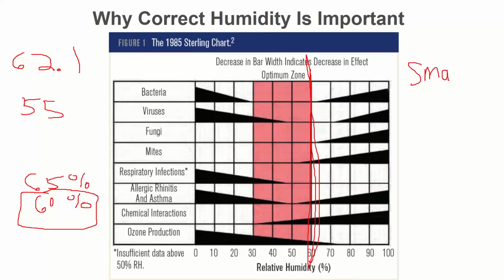The way to do it is smaller equipment. Stop oversizing things. Everything is oversized, literally. I could give you a 1-hour discussion on oversizing. It's a big problem. Everything gets oversized because every designer is deathly afraid that it's going to be 107 degrees and they won't be able to keep up. It's crazy. You need smaller equipment so it runs longer, so the evaporator stays wet longer, so we dehumidify more.